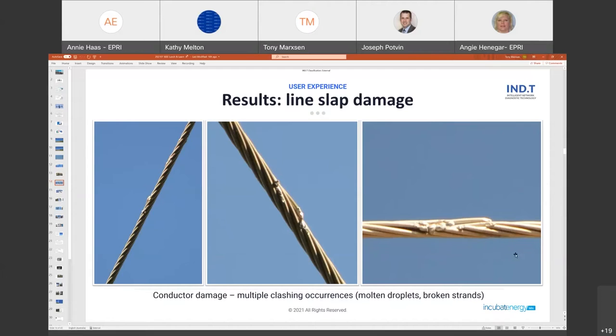It is interesting that these particular instances were far out along the distribution circuit, in a very windy area, and the arcs actually blew out before the protection operated. So this particular location was seeing repeated conductor slaps when the wind was in the right direction and at the right speed, but the line was not tripping. We could see along this span multiple instances of this type of damage.